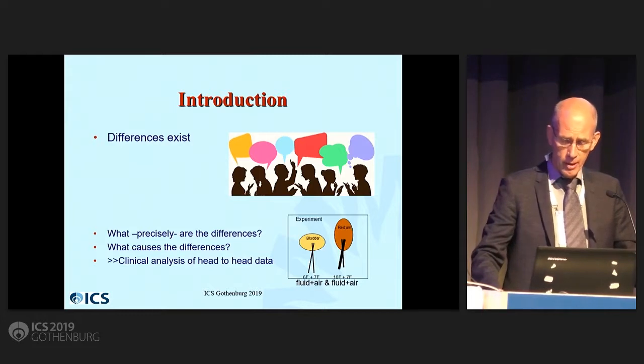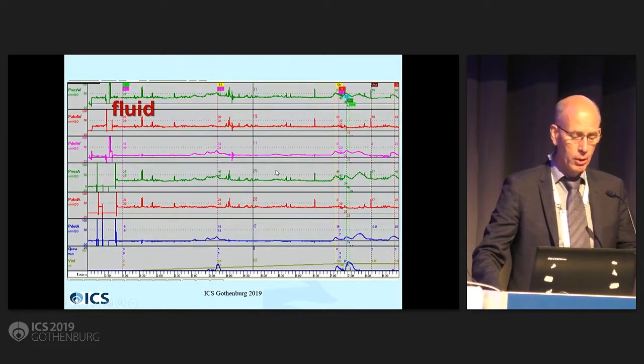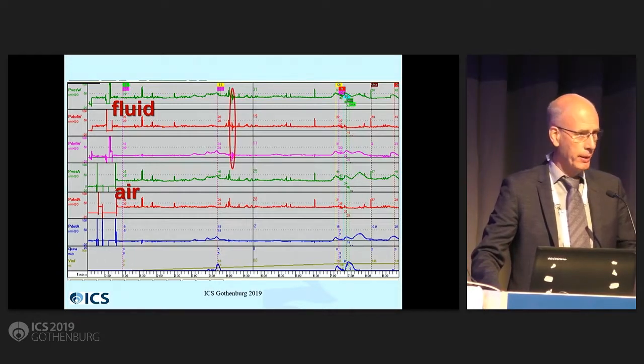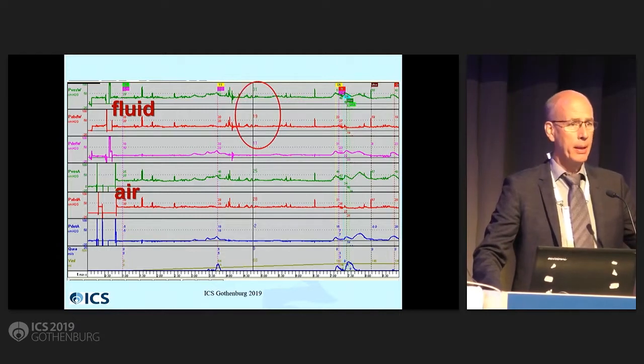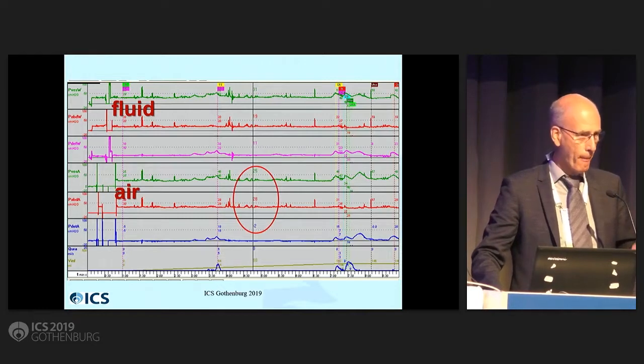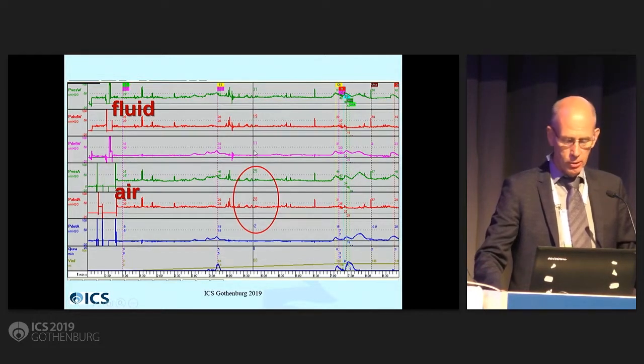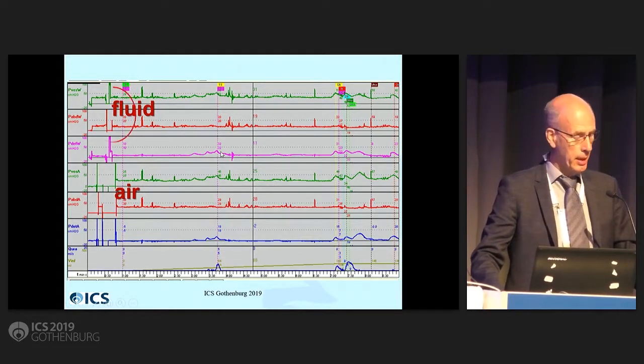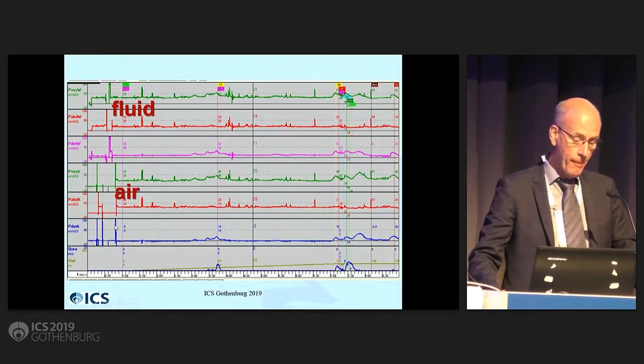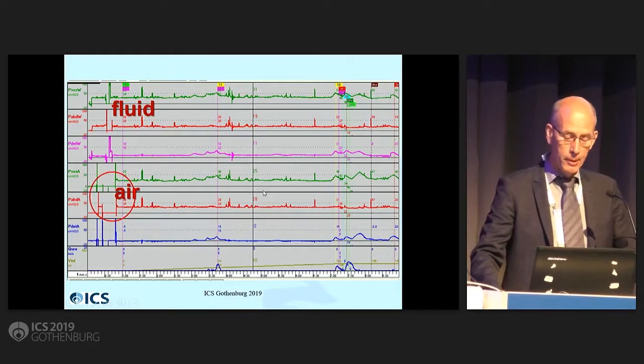I presented results already in Florence. Head-to-head, one and another pair of catheters inserted after ethical board review. This is one of the results: fluid-filled and air-filled — and you see the typical tube-wagging artifact from the fluid system, which is lacking in the air-filled system. But you also see baseline differences between the pressures measured. The green lines are vesical and the red lines are rectal. They are zeroed to atmosphere properly, but then you still get the differences.